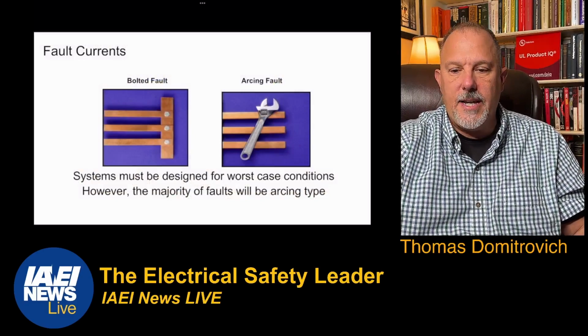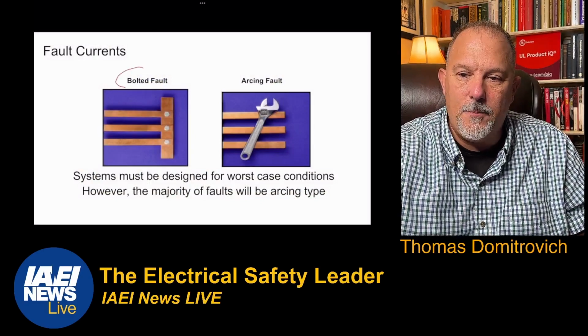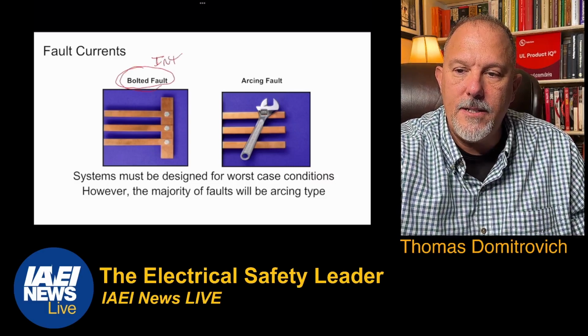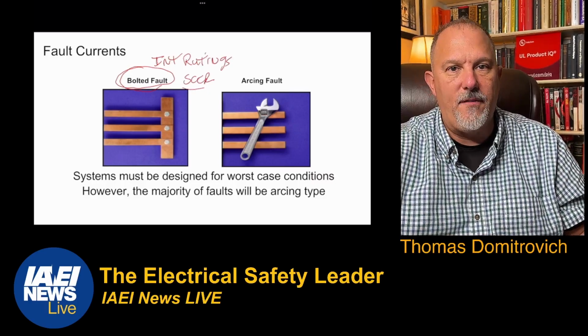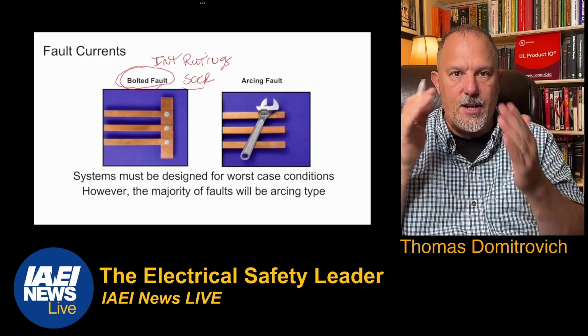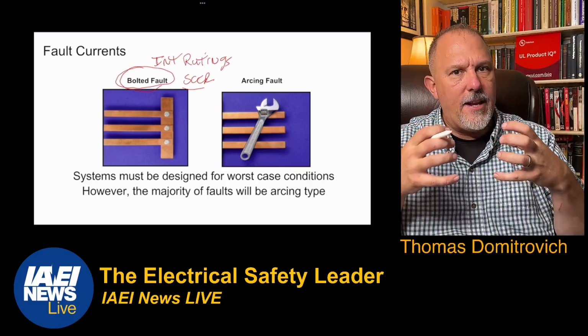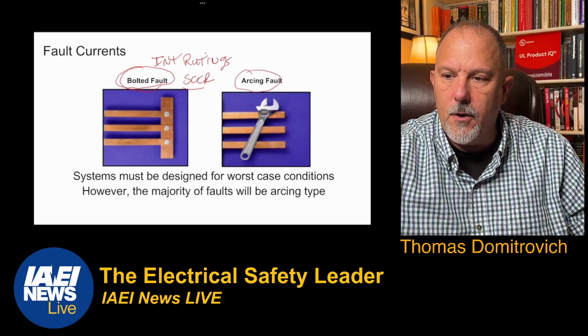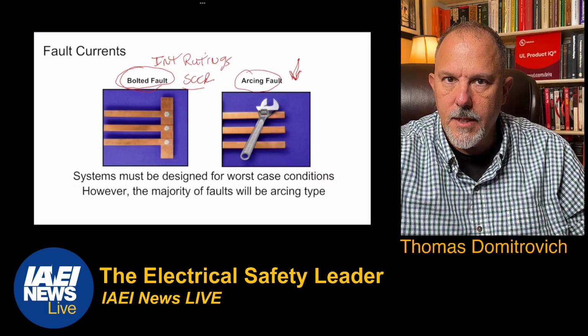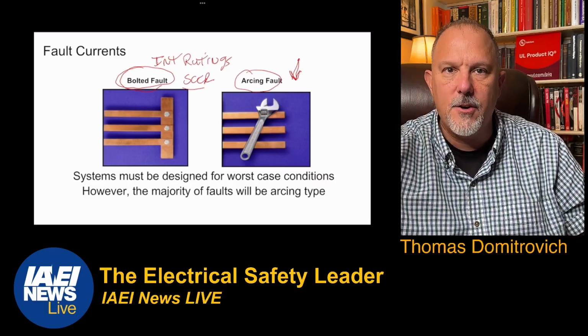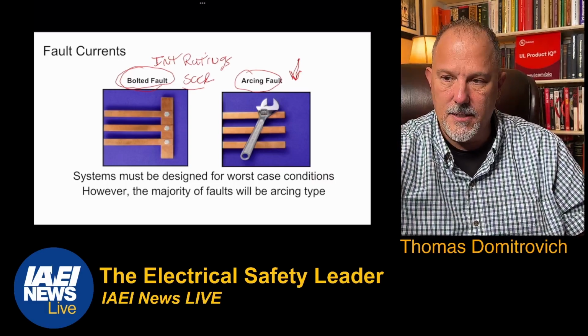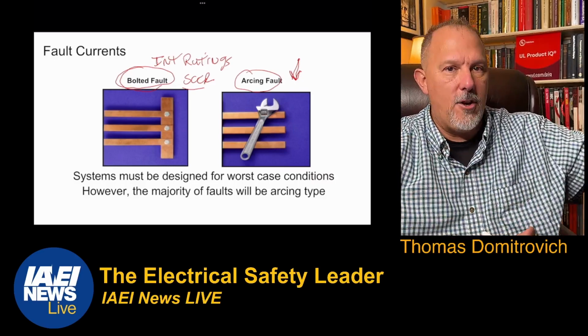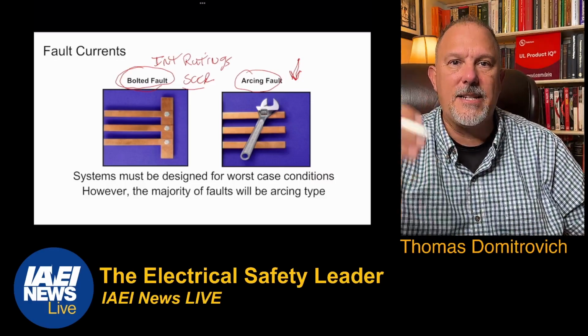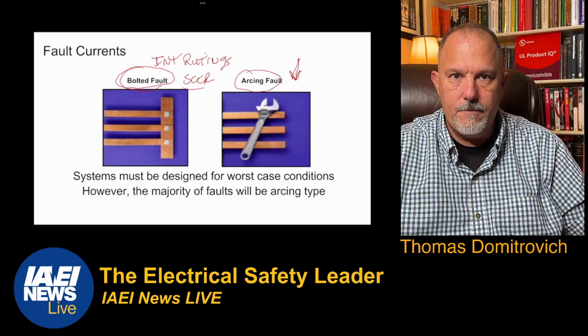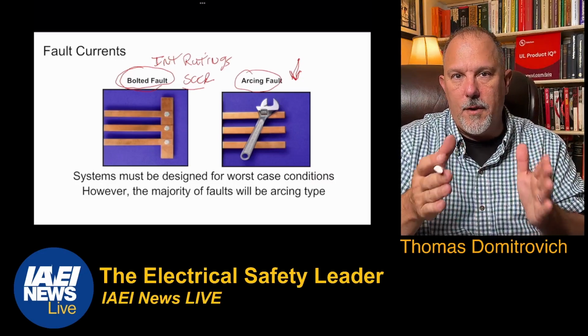So we have to design for the worst case conditions, right? But in some cases, the bolted fault current for interrupting ratings and short circuit current ratings, that is what I will do my equipment evaluations. That's the worst case for an overcurrent device trying to open and clear the fault, and the worst case for a piece of equipment and all of those magnetic forces letting that current pass through it. The arcing fault, though, is a lower value. The lower values of arcing current can produce higher levels of incident energy, and I'll help you understand why that's the case. But the worst case condition for interrupting ratings and short circuit current ratings may not be the worst case condition for an arc flash calculation.